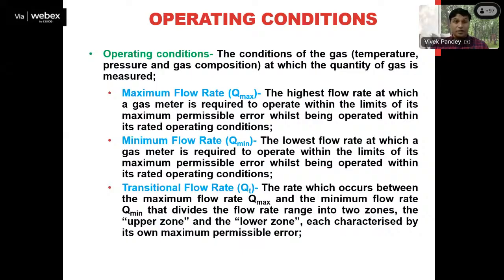Now, when we are talking about the maximum and minimum flow rate, it is a specified range of flow rates, specified by the manufacturer and certified by the regulatory authority, that within this flow range, if the gas meter is operating, it will give you the desired level of accuracy. That means any error observed during the operation of the gas meter, if it is operating within the minimum to maximum flow rate, will be within the maximum prescribed tolerance. Fine.